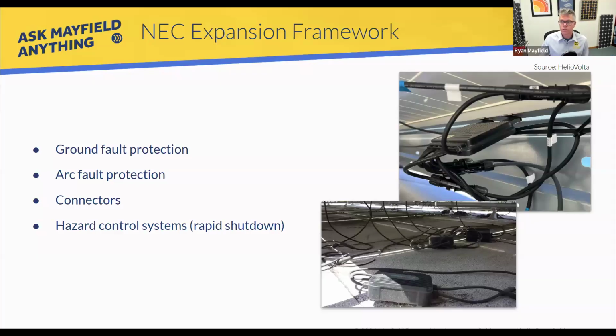Let me speak more to what happens in the field and the reality of the situation most of the time, because I've seen it. We went from ground fault protection being just CTs, then inline fuses, and now arc fault detection. Every time we introduce those things, we're introducing a different way to capture, troubleshoot, and identify issues, because you're adding layers to systems, and they do fail.